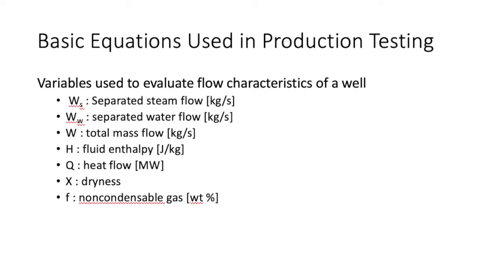Some basic equations are used in production testing. In most conditions it is assumed that steam and water properties of a geothermal well are at saturation conditions and local pressure. However, some wells do produce dry steam and superheated conditions may exist. In that case, steam properties must be evaluated at the temperature and pressure of the steam itself.